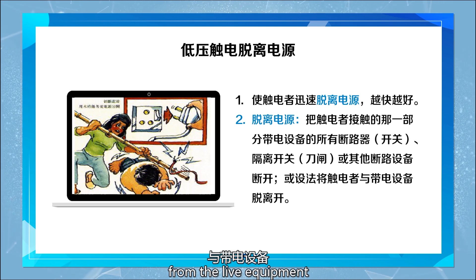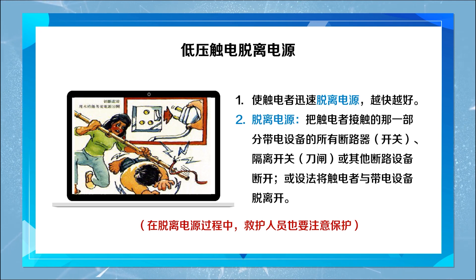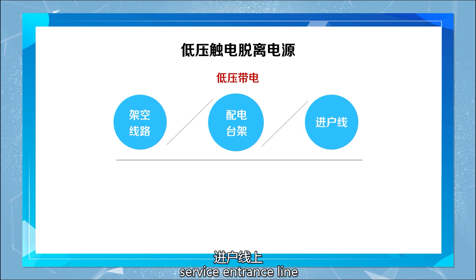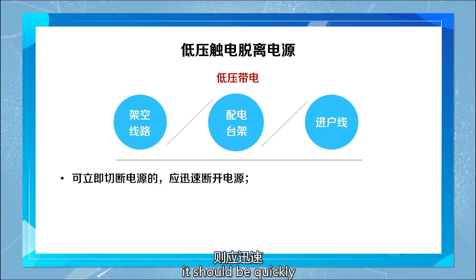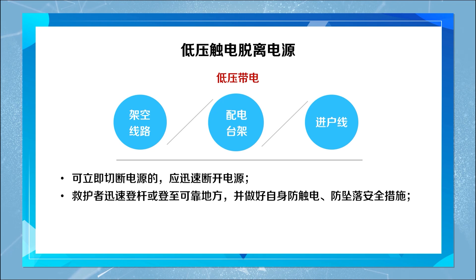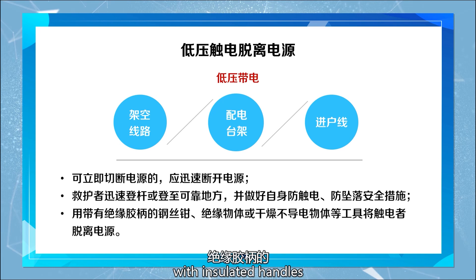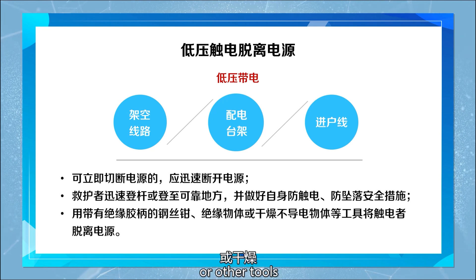From the live equipment, during detachment, the rescuer must protect themselves. If the electric shock occurs on a low voltage live overhead line or distribution platform service entrance line, for those that can immediately cut off the power source, it should be quickly disconnected. The rescuer should quickly climb to the pole or climb to a safe place, taking anti-electric shock and anti-fall safety measures. Use insulated wire cutters with insulated handles, or dry non-conductive objects or other tools to separate the electrocuted person from the power source.